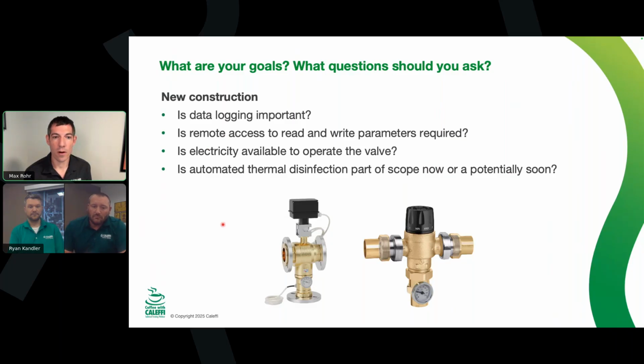That's a good point—are you going to do that in the future? We still see a pretty small percentage of digital mixing valve sales in North America where people are doing Legionella management with thermal disinfection today versus saying they're going to start that as soon as the valve's installed. A lot of people think it might be a good idea to have that option. That's a good case for digital, because most digital mixing valves people set up are just running a simple set point like 113, but you could change the program later and enable those features instead of ripping it out and installing a different valve. So there's a flexibility advantage with digital.